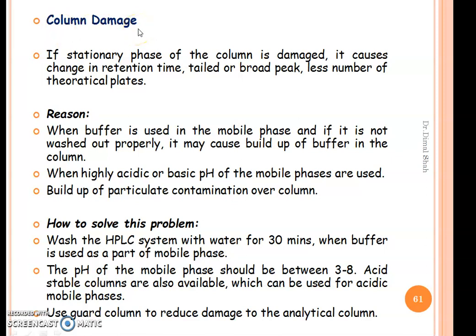Column damage. If the stationary phase of the column is damaged, it causes a change in the retention time, tailed or broad peaks, or a smaller number of theoretical plates. What is the reason why the column is getting damaged? When buffer is used in the mobile phase and it is not washed properly, it may build up in the column and ultimately cause column damage.